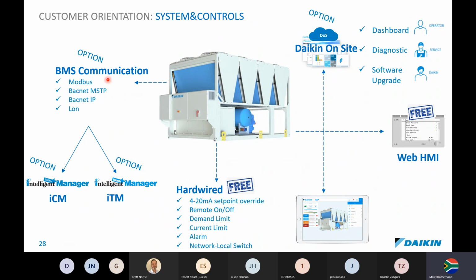Also on this system and controls, we offer BMS communication for Modbus, BACnet over IP or LonWorks. Further options that we offer are the Daikin Chiller Manager or the Intelligent Manager. We're also promoting as an option Daikin on Site, which is a virtual cloud-accessible platform with dashboards where an operator, or a technician, can go on and look at different faults. It's all accessible on a tablet with Daikin on Site.